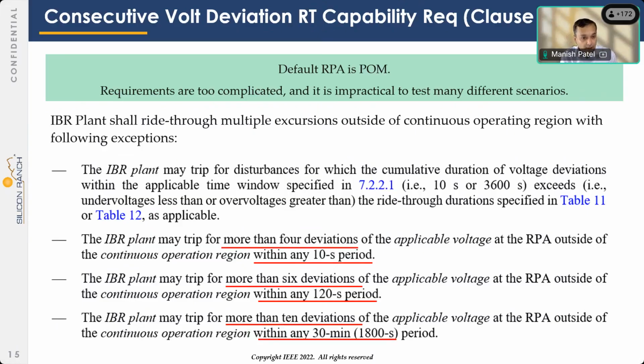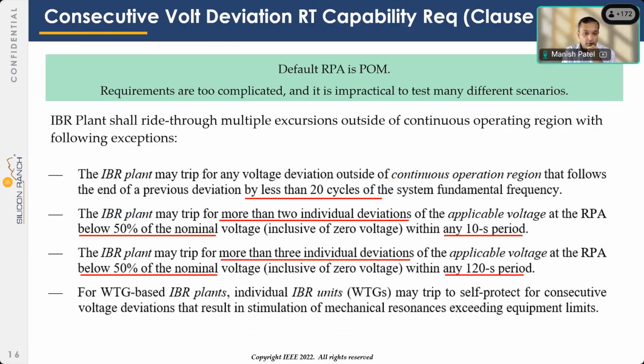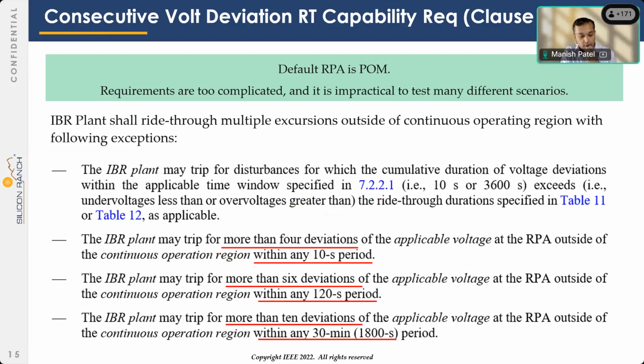It says IBR plant shall ride through multiple excursions outside of continuous operating region with the following exceptions. And look, I'm not going to read all these exceptions, but I'm going to go back and forth on those two slides for a second. Okay, this is one set of exceptions that you see on the screen, and then there are four more. When you start reading those exceptions and understanding that anything not within this exception plan needs to ride through, there could be hundreds of scenarios.